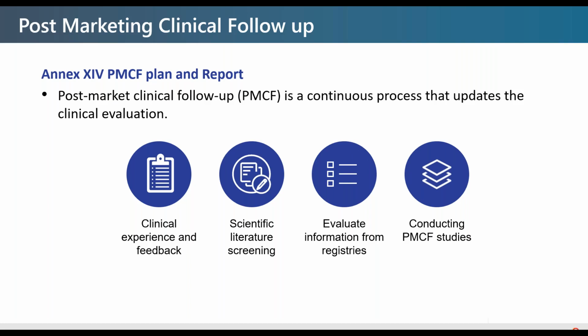I've kind of got them backwards on there, but we don't want to have to do a clinical study on everybody, right? So we don't want to be forced to do PMCF studies on everyone, but that is definitely one of the things we could do. We can go back to that registry information that I talked about and evaluate that. And that is also clinical data, right?